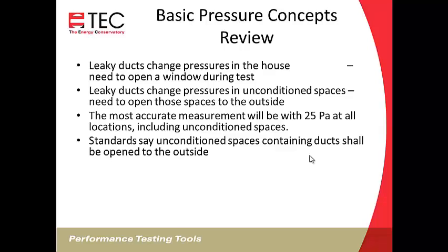Standards say that unconditioned spaces containing ducts shall be open to the outside, so although that's not always possible or practical, we're not saying bring a Sawzall around and always make a hole to relieve that pressure. But if there are doors, windows, access panels in those attics or crawl spaces that can be open to the outside vents, then we want to do that.